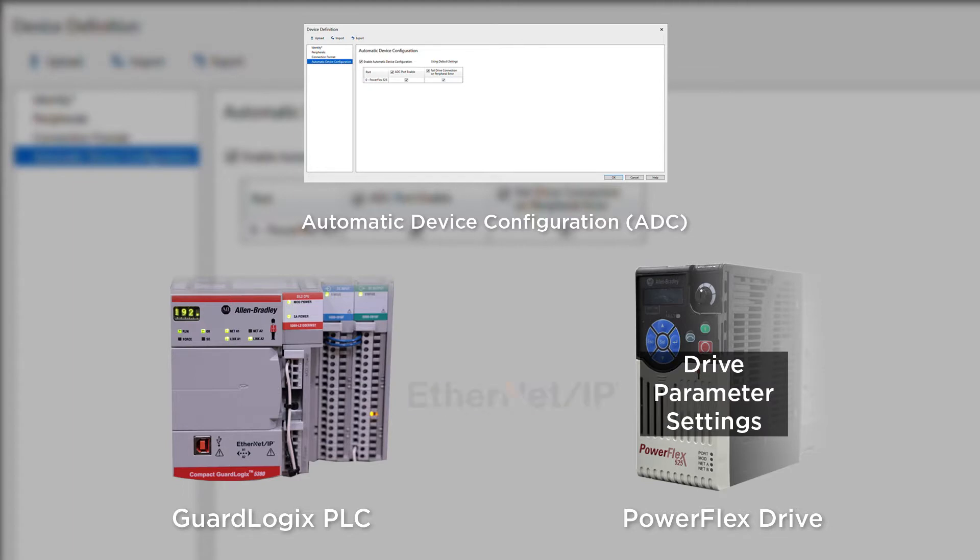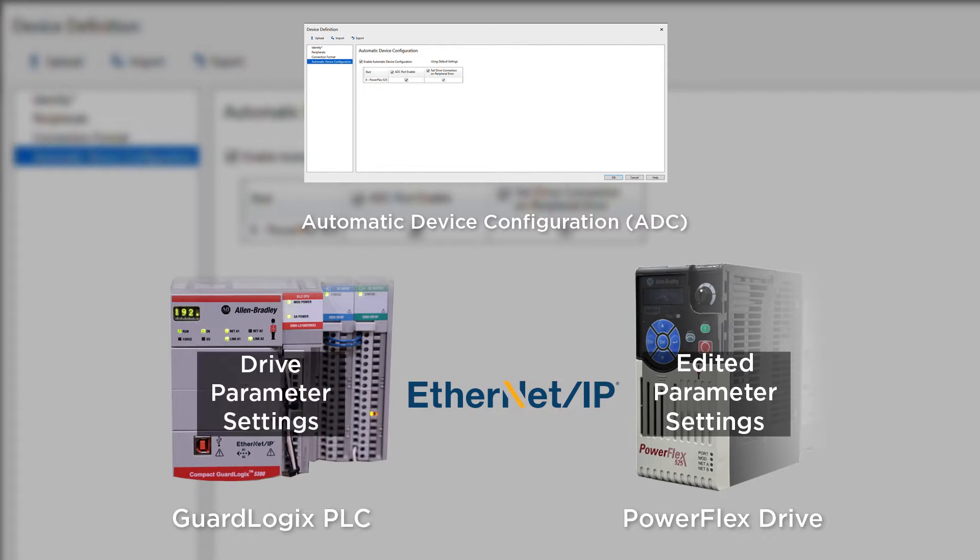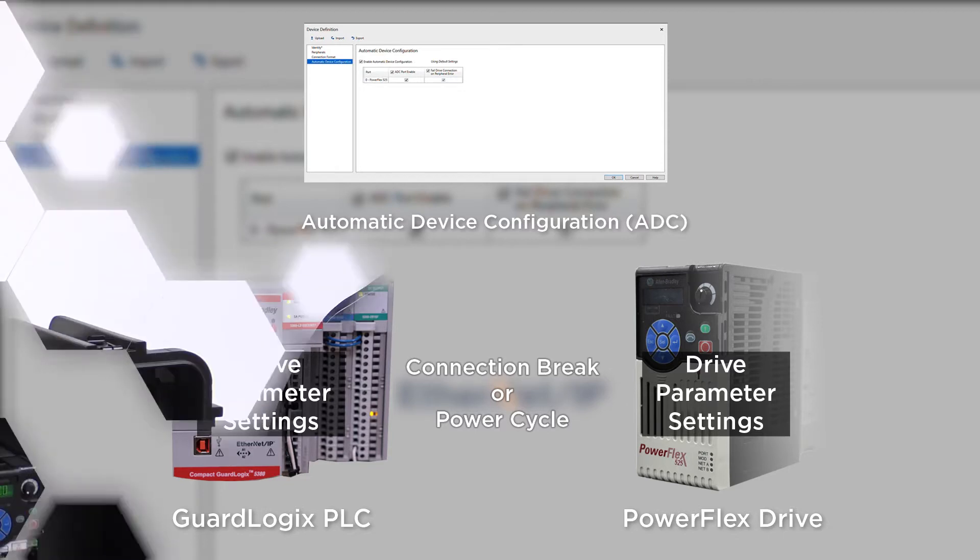ADC allows the controller to automatically load the saved drive parameter settings into the drive. This occurs when the Ethernet IP connection is initially established with the drive and the controller detects a difference with the saved configuration. This means you can still make edits to the drive parameters on the fly, but any parameters changed at the drive and not saved in the configuration file for the PLC will automatically be overridden next time an Ethernet break or power cycle occurs.